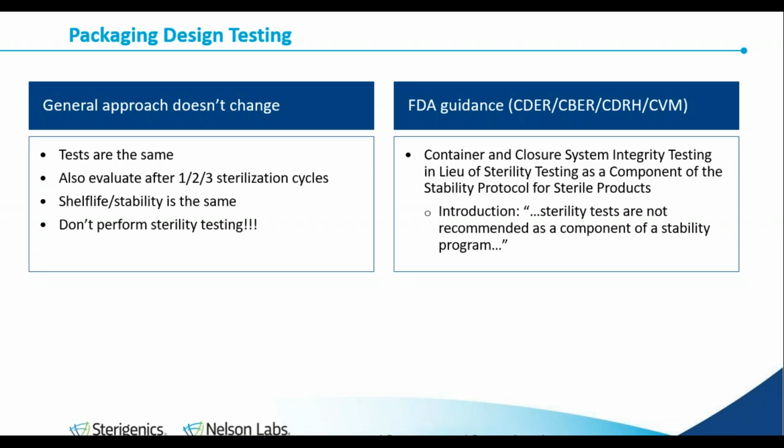And there's a really good FDA guidance document, and all 4 branches of FDA participated in this. So CDER, CBER, CDRH, and CVM all have their names on this document, and the title is Container Closure System Integrity Testing in lieu of sterility testing as a component of the stability protocol for sterile products.